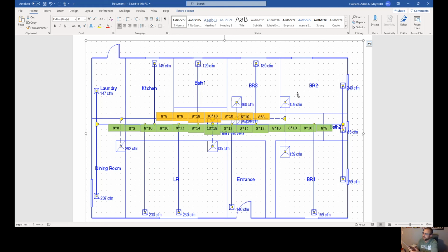And so just for an example, let's say that we're moving 1100 CFM at 0.1 like we were. So go back up to that and just remember what that was. So 1100 CFM at 0.1 looks like it is 8 by 22 or so, or 10 by 18.